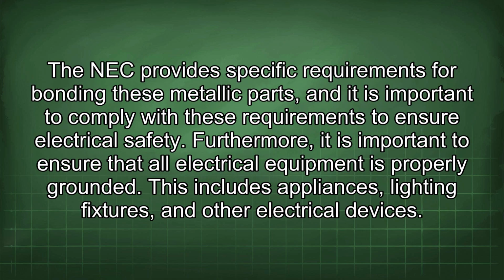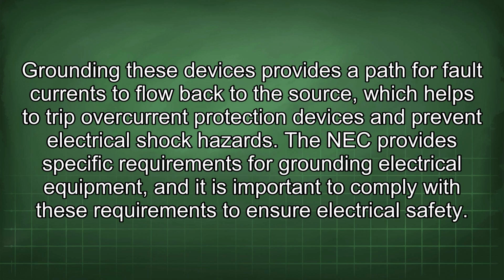The NEC provides specific requirements for bonding these metallic parts, and it is important to comply with these requirements to ensure electrical safety. Furthermore, it is important to ensure that all electrical equipment is properly grounded. This includes appliances, lighting fixtures, and other electrical devices. Grounding these devices provides a path for fault currents to flow back to the source, which helps to trip overcurrent protection devices and prevent electrical shock hazards.